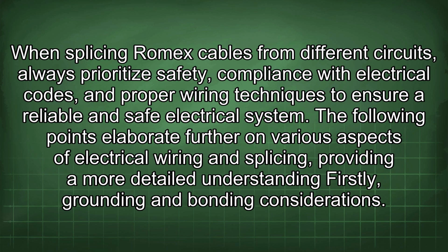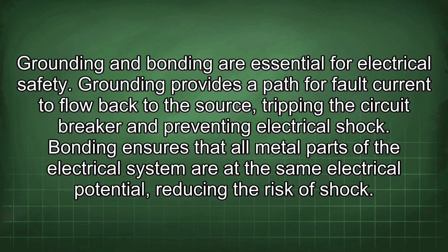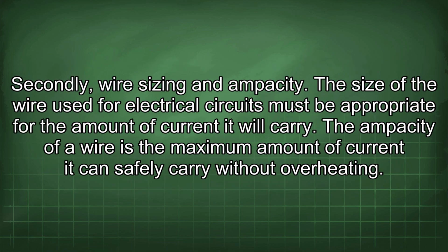Firstly, grounding and bonding considerations. Grounding and bonding are essential for electrical safety. Grounding provides a path for fault current to flow back to the source, tripping the circuit breaker and preventing electrical shock. Bonding ensures that all metal parts of the electrical system are at the same electrical potential, reducing the risk of shock. Secondly, wire sizing and ampacity.